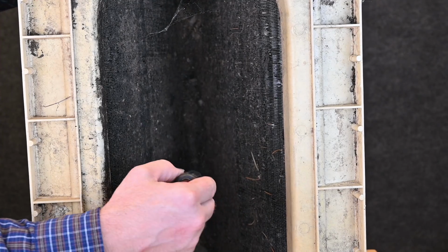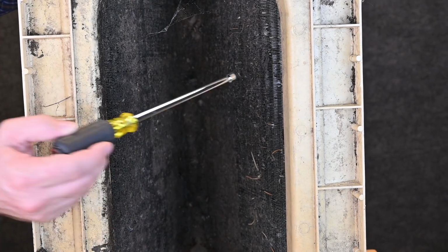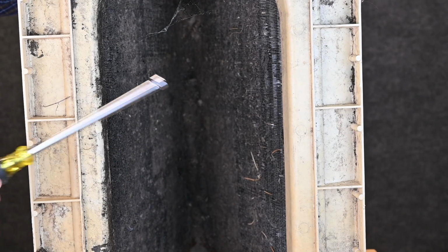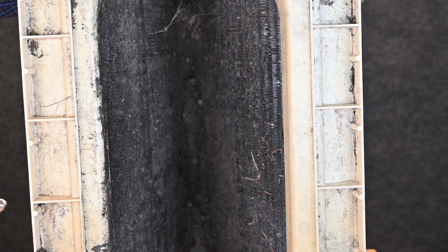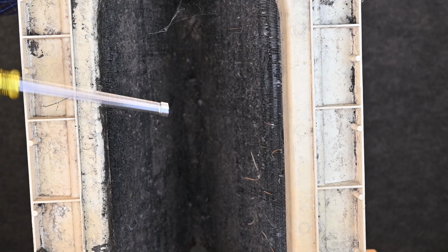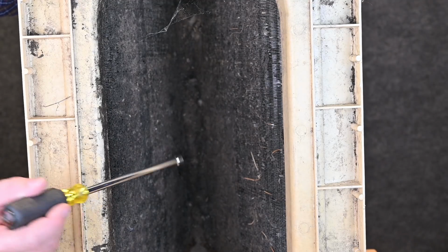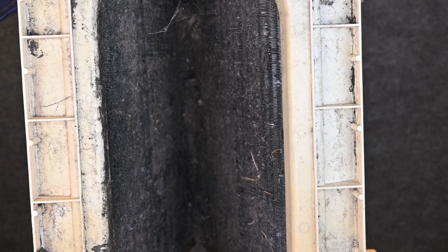There's all kinds of hair inside of there. There's all kinds of buildup inside of there. It is horribly, horribly dirty. So it's important to look on the underside. And there's several ways to do that. In the old days, we would try to work a mirror under there to see it. But nowadays, we have different types of endoscopes or little cameras on the end of wires that we can stick in there that hook even to our phone. And we can take a look up inside of here and we can see what it looks like.